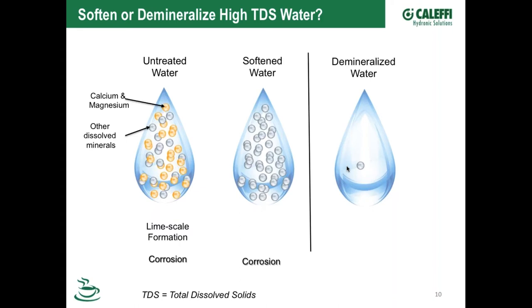So what I need to know when I look at a sample of water on your job site: I'd like to know the hardness of the water, and I bet most plumbers tuned in today have a water hardness test kit, just a little dropper kit. I'd also like to know the TDS, total dissolved solids, which is all the minerals in the water. It won't tell me exactly how much is chlorides versus calcium, but it gives the total amount of solids. And then I'd like to know the pH of the water - is it acid-based or going toward alkalinity - because that affects some of the components in the system too.